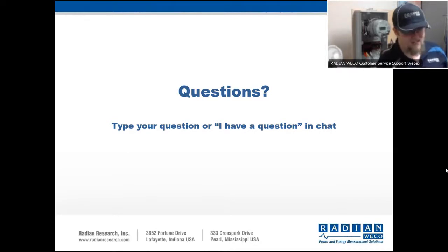How long does DMAG take? About 5 seconds. It is a very quick process. I click the DMAG button and it does its thing in about 5 seconds. Ramp up burden, ramp down burden, it's done. It's a very quick process.